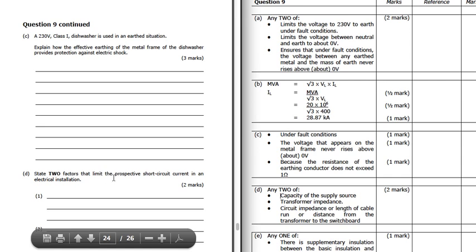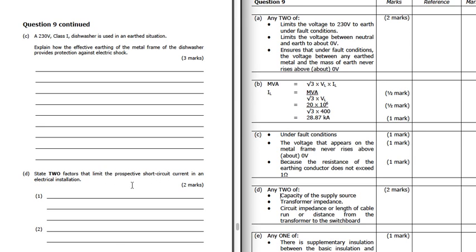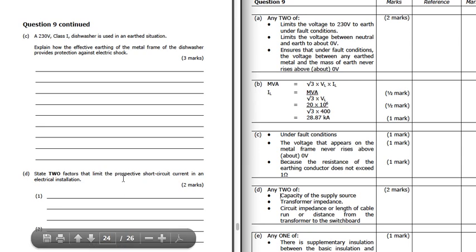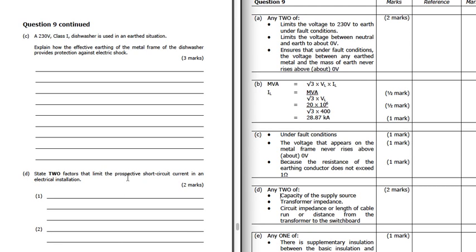Two factors that limit the prospective short circuit current in an electrical installation. So what's going to limit the amount of current that could flow under fault conditions? Well, it's going to be the capacity of the supply source. It's going to be the transformer impedance. And it's going to be the circuit impedance, or the length of cable run, or the distance from the transformer to the switchboard. So all of this is going to affect the impedance of the circuit. So it's the transformer impedance, the circuit impedance, and the capacity of the supply. So the capacity to push out the current, and this to try and stop the current.